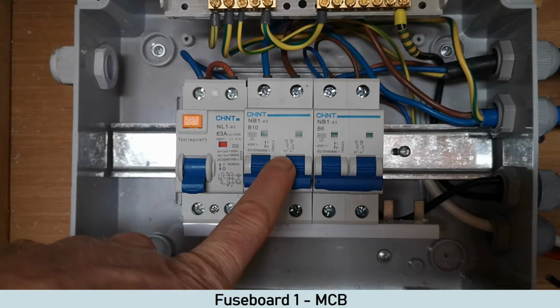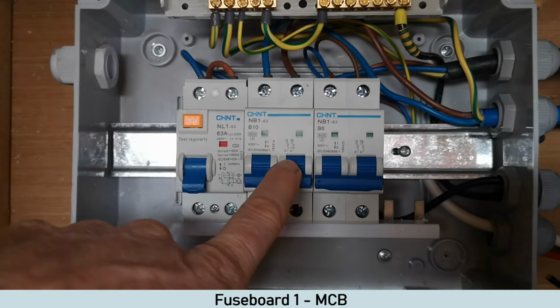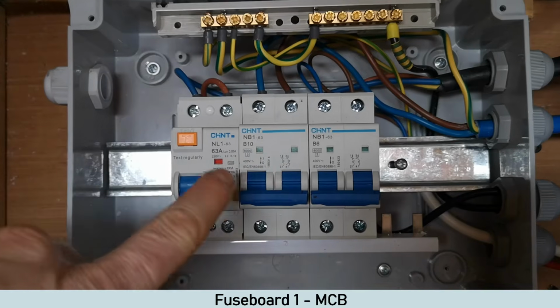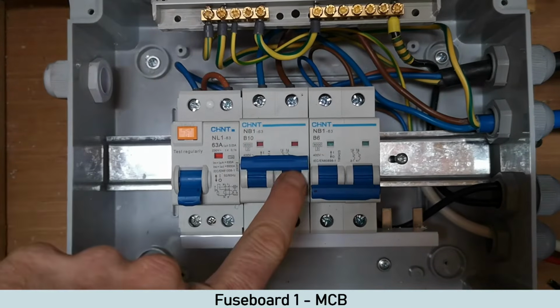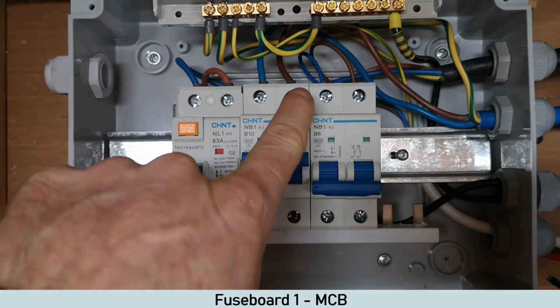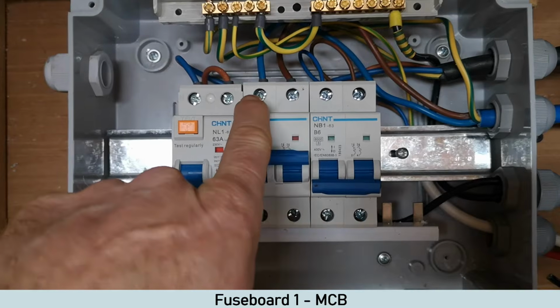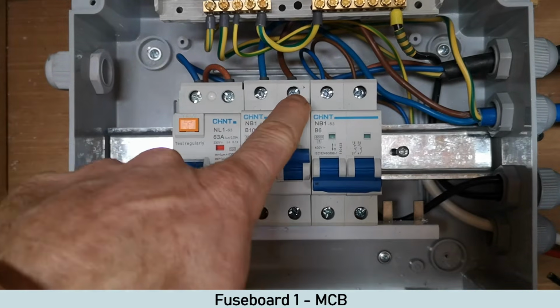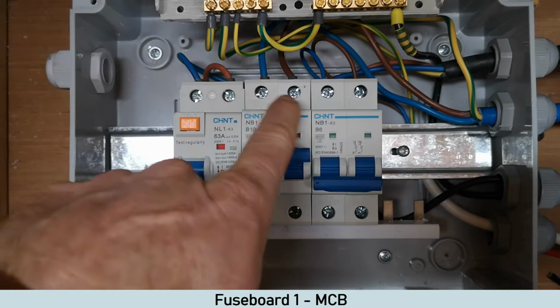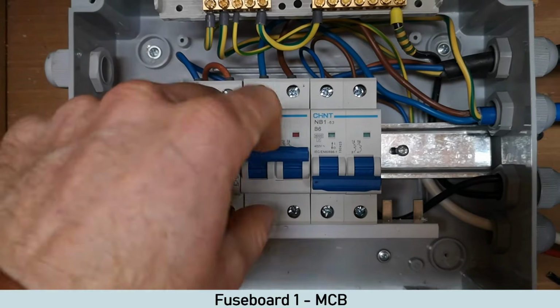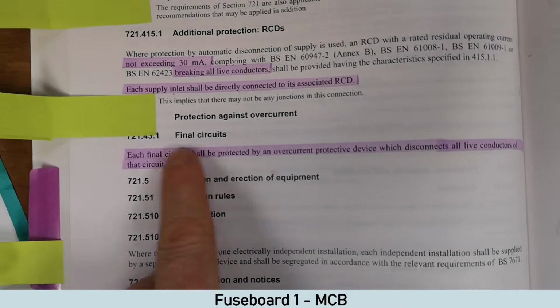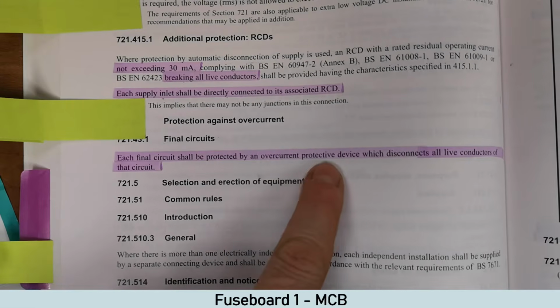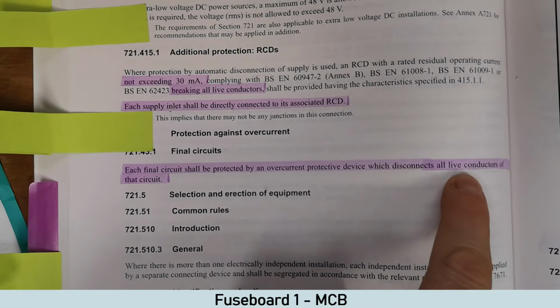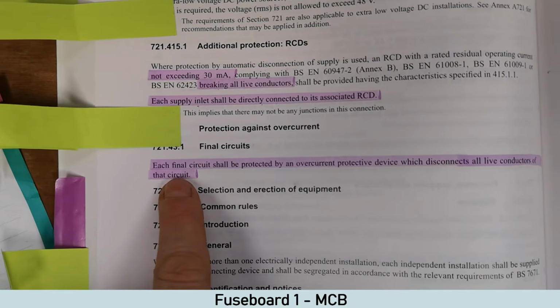Circuit breakers in a fuseboard in camper vans must be double pole, and double pole means there's two switches. So it's double pole, and it disconnects the live and the neutral, the same as the RCD. So it must disconnect both live conductors, so live and neutral. In the regs, you can see here that each final circuit shall be protected by an overcurrent protective device which disconnects all live conductors of that circuit.